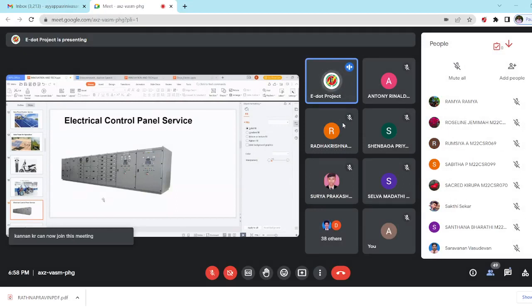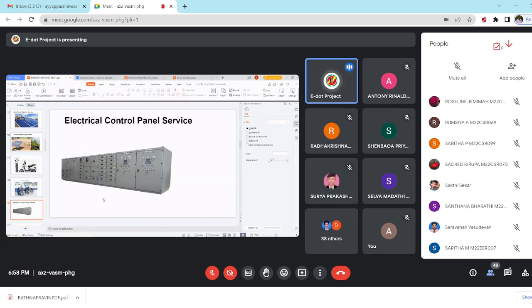Then the protection system. We need overload protection, under voltage protection, high voltage protection, earth fault protection, unbalance protection. So many protections are needed to trip the circuit breaker, meaning to protect the sources. So the second control panel system is the protection system.